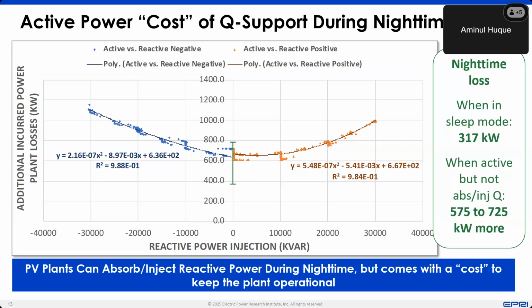So that's the first question. The plant has many inverters. A transmission connected plant has two levels of transformers: each power block has its own medium voltage transformer, then you have a high voltage transformer. Then of course there are long AC cables, or the AC collection system, throughout the plant. So there are losses in addition to whatever active power the individual inverters need to stay operational. That's why we cannot just multiply the inverter power by X and get the total plant active power requirement, because the plant has other components also. So again, this is one example of a real plant doing it and how much it costs to do it.